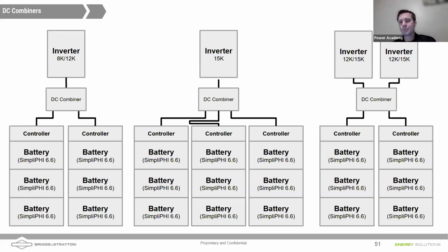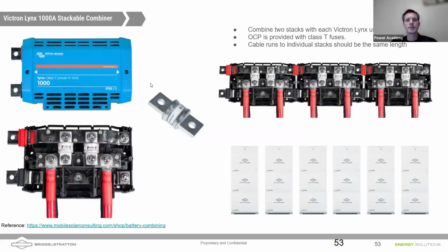If you're paralleling inverters, it doesn't matter if it's a 12K Sol-Ark or a 15K Sol-Ark. Anytime you're paralleling inverters, you have to have a single battery bank. So you do need a DC combiner, and then you'll feed each inverter that's parallel. This could be up to 12. You'll feed each inverter that's paralleled off that common DC bank. You never want to feed one inverter from one bank and another inverter from another bank. Always with paralleled inverters, combine your DC batteries.